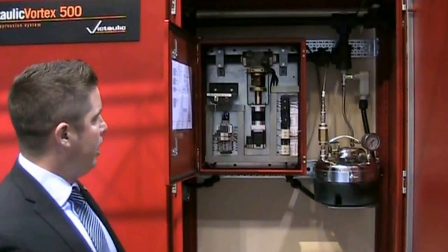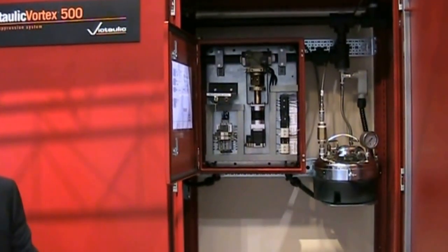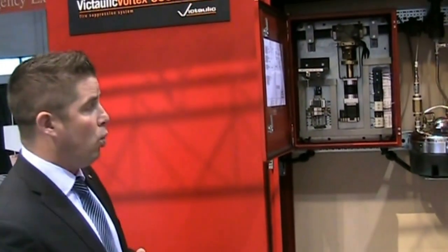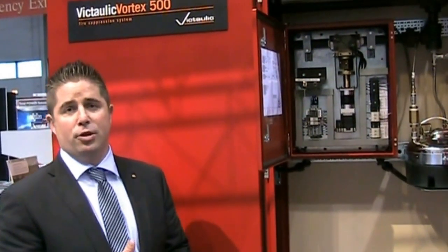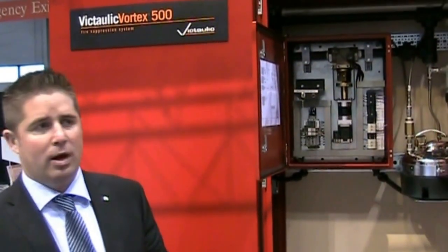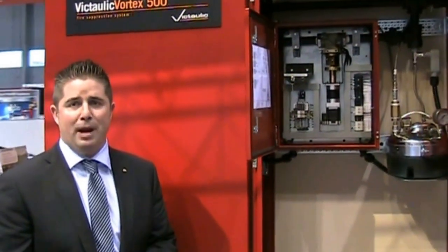Inside our panel, we house our Victaulic Needle Valve. This is our regulating valve, which brings the pressure down from 3,000 psi in the cylinders down to 25 psi through the piping. Another benefit of this is we can use low-pressure standard carbon steel piping with Victaulic Groove Couplings. The water pressure is pushed through by diverting a little bit of the nitrogen into the water tank, also at very low pressure.